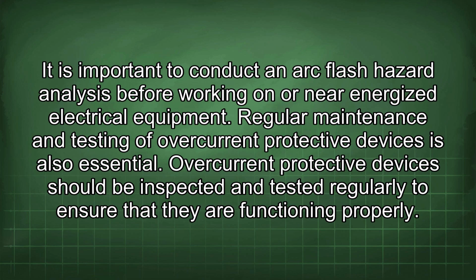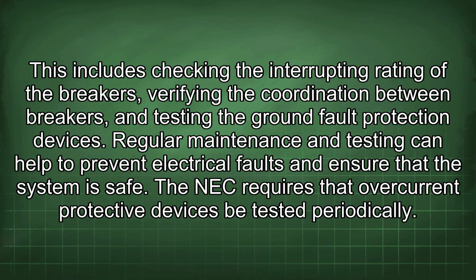Regular maintenance and testing of overcurrent protective devices is also essential. Overcurrent protective devices should be inspected and tested regularly to ensure that they are functioning properly. This includes checking the interrupting rating of the breakers, verifying the coordination between breakers, and testing the ground fault protection devices. Regular maintenance and testing can help to prevent electrical faults and ensure that the system is safe.